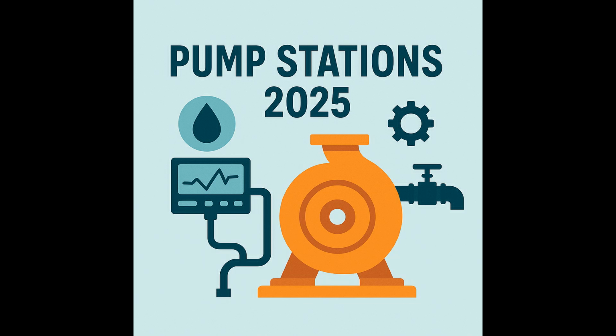Just in case. Exactly. While the upfront cost of buying and storing a spare pump can seem significant, the cost of extended downtime, potential environmental issues, and emergency repairs resulting from a catastrophic pump failure is almost always far, far higher. Right. The cost of not having it. Precisely. And it's not just the cost of the pump itself. It's crucial to budget for the skilled labor needed, the OT technicians, the electricians, the mechanics for the installation, the control programming, and the wiring during a replacement, which often happens under pressure.